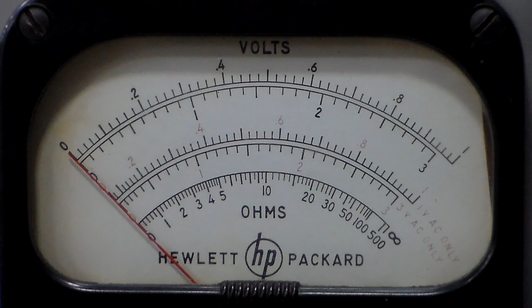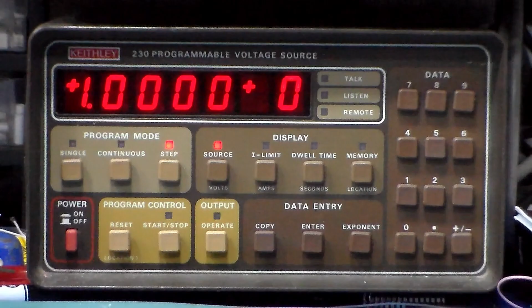Next, we should be able to go and check the calibration, and for that I'll just show you, we're just using a Keithley 230 programmable voltage source, and while the Keithley, this particular unit anyway, is not up to the level of a Fluke calibrator with say 7 or 8 digit precision, it's way better than I need to actually calibrate the HP 14B, at least on DC volts. Now with the Keithley 230 supplying 1 volt into the HP 14B, you can see that it's slightly off of 1 volt, so we'll just get around the back here and adjust until we get close on 1 volt, and you can see that that's pretty right now.